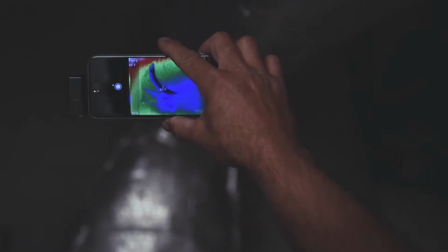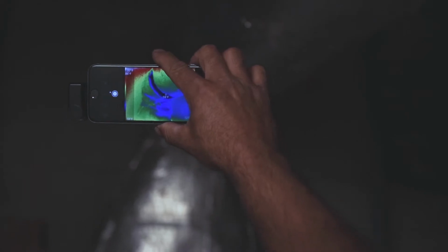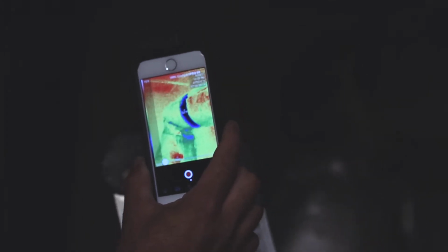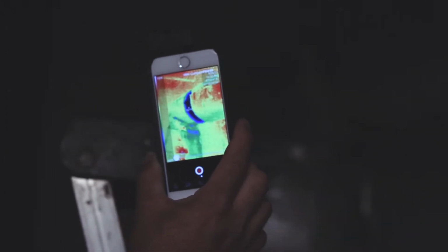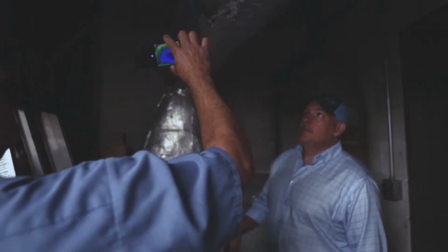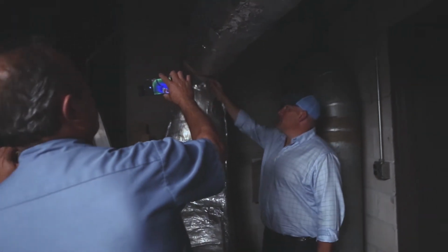Ooh, what's that? Look at that dark. There, I have a huge thermal loss. It's actually missing insulation right there, the ductwork, the duct wrap. Look at that. Yeah. With that thermal scan, you could immediately see the difference. 73. So 73 surface temperature and 61.